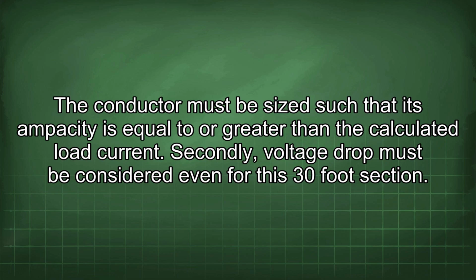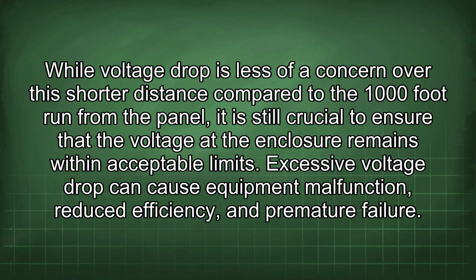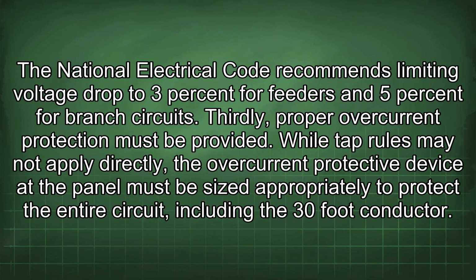Secondly, voltage drop must be considered even for this 30-foot section. While voltage drop is less of a concern over the shorter distance compared to the 1,000-foot run from the panel, it is still crucial to ensure that the voltage at the enclosure remains within acceptable limits. Excessive voltage drop can cause equipment malfunction, reduced efficiency, and premature failure. The National Electrical Code recommends limiting voltage drop to 3% for feeders and 5% for branch circuits.